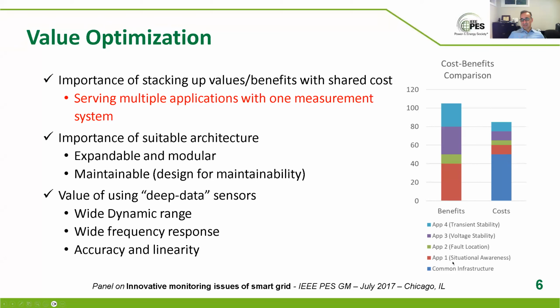You still haven't done much, but then you install one software application for situational awareness that reads the PMU data, knows the model of your system or geography, and can tell you, oh, the phases are bad or good, or voltage is too high or too low. That's the benefit. So if you look on the benefit side, the base cost doesn't have a benefit. The application that we install, the function, that's the one that has a benefit. So you have some significant cost for base infrastructure and a little bit of cost for that application. On top of that, you could have multiple applications. The additional applications are usually marginal additional costs because they share the same base cost of the sensors and devices and hardware that were there.